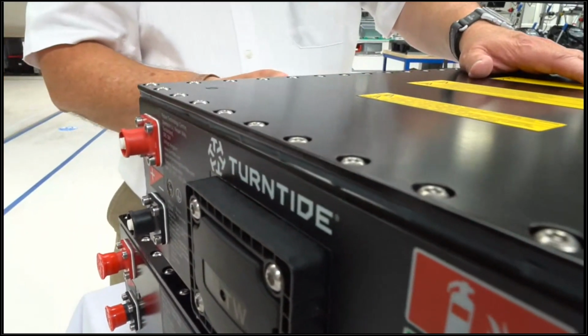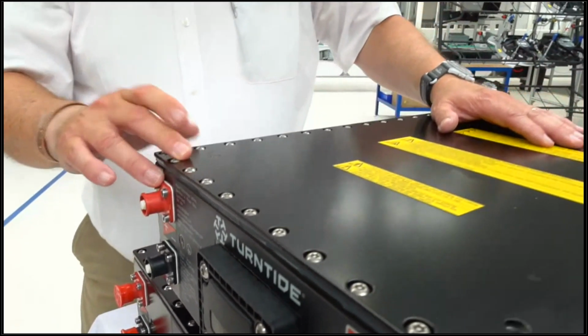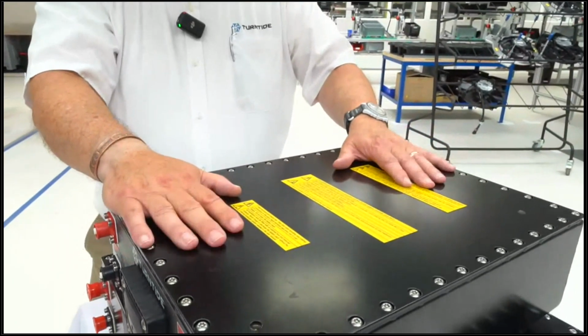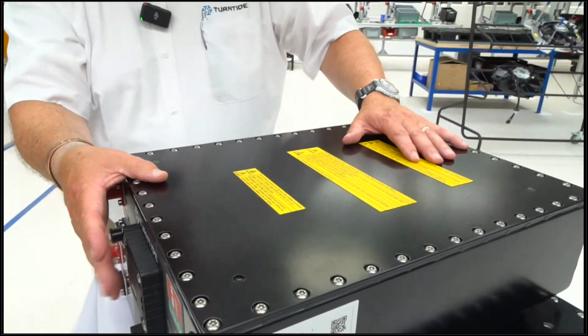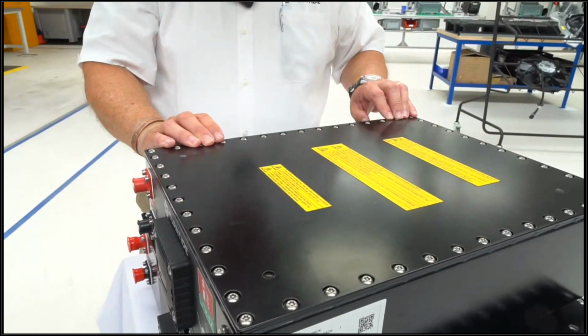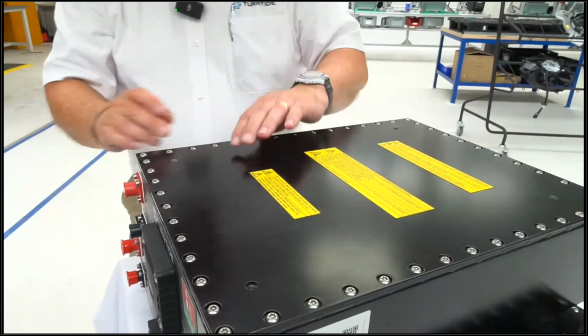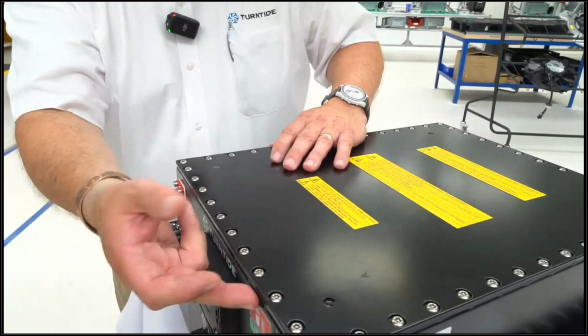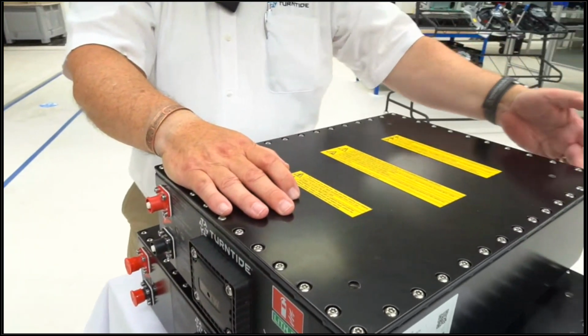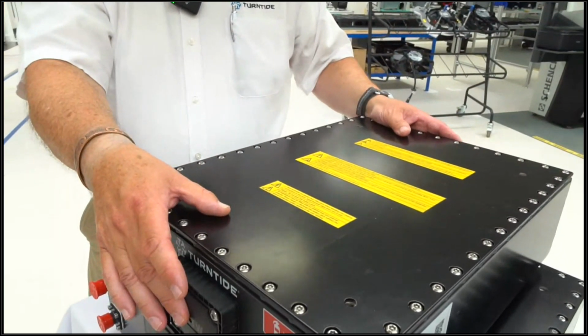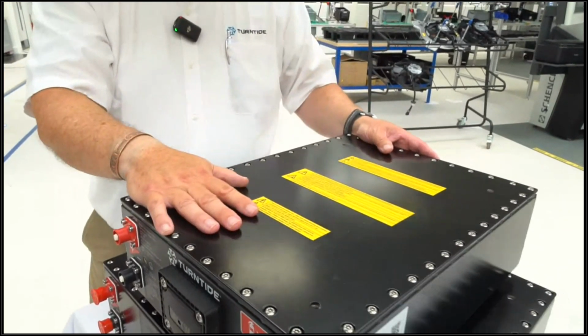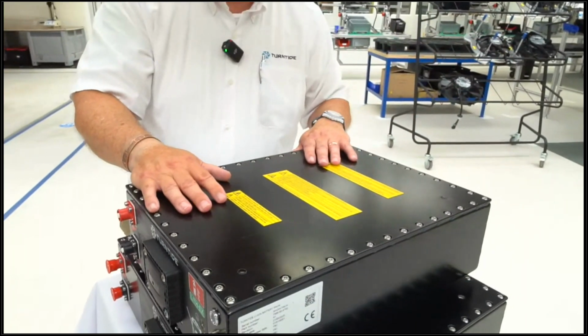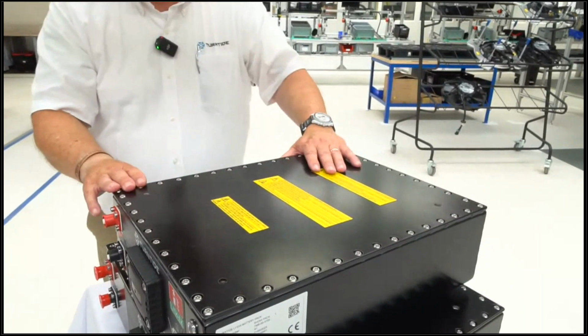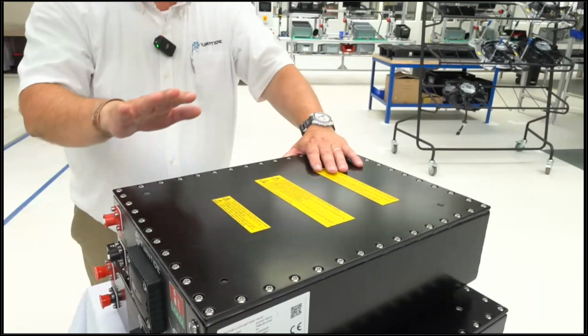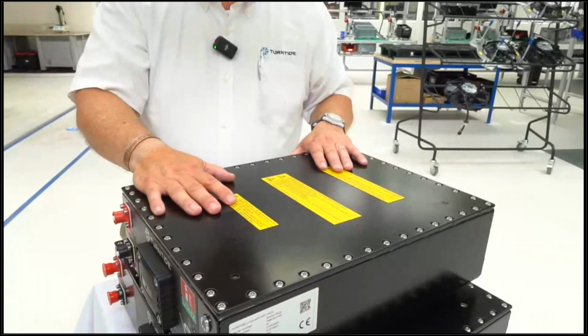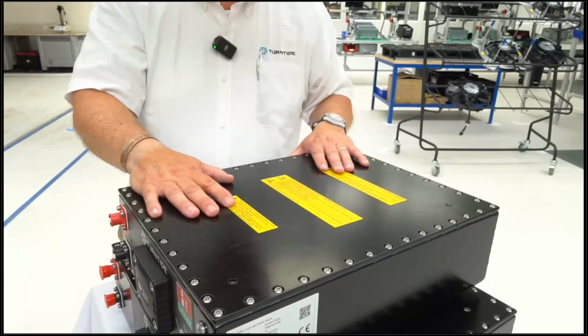The gasket survives both the temperature and the pressure, but really, to survive the pressure and let the vent do its job, this number of fastenings on the top is needed to make sure there's no chance of gases leaking anywhere other than through the vent. It looks like a lot of fastenings, and I'm sure production operators have some concerns about adding these, but that's what we needed to do to get this pack CE marked and passed.